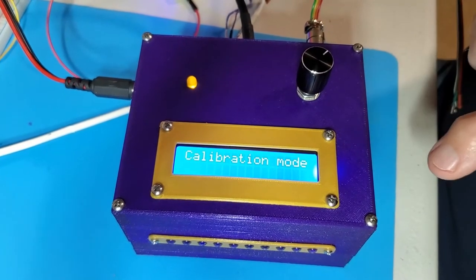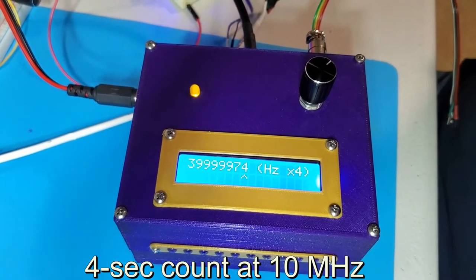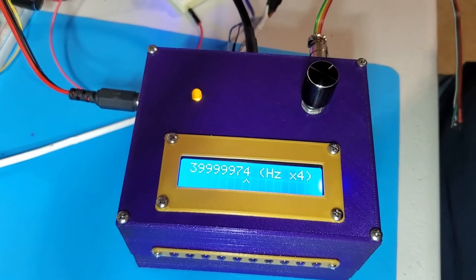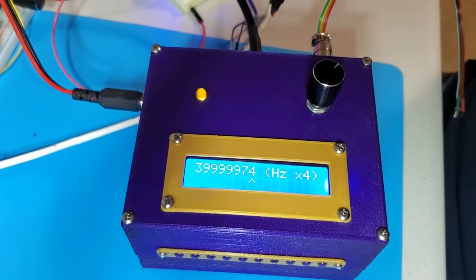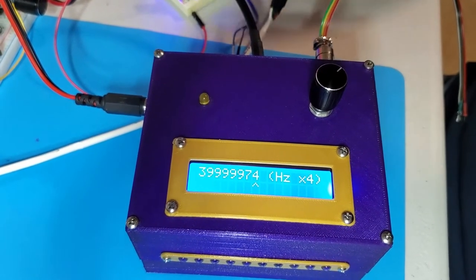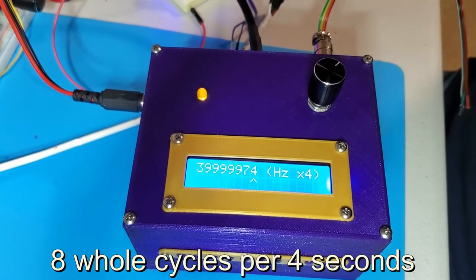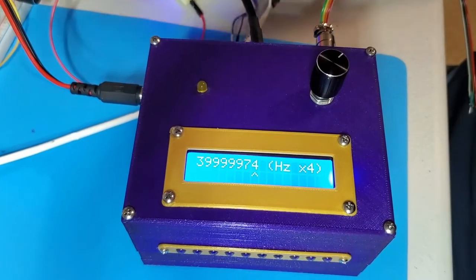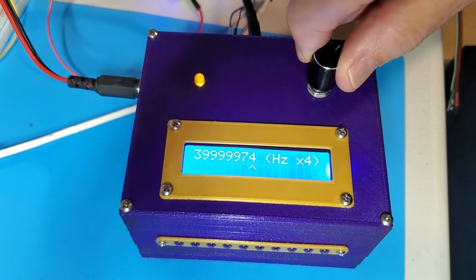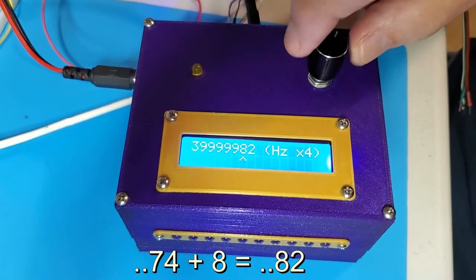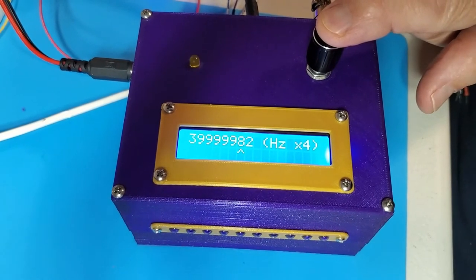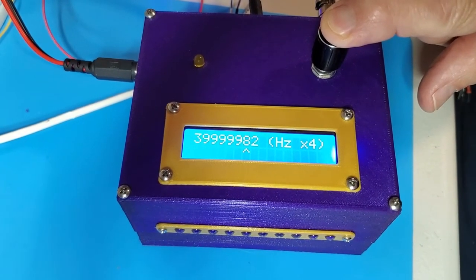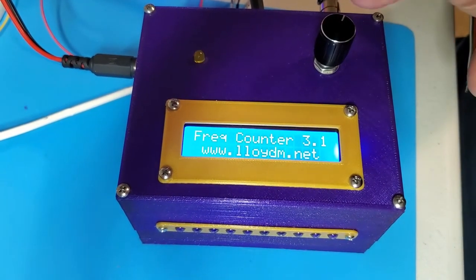Two Hertz would be eight count over four seconds, but two Hertz at seven megahertz, not 10 megahertz. But anyway, I'm just going to pretend that's what we want and go down to here and then skip a digit and go up one. We'll see what happens. I may have completely missed on it, but we'll see what happens. We save that calibration and now we're ready to take another measurement.